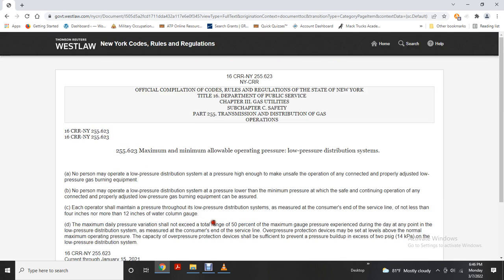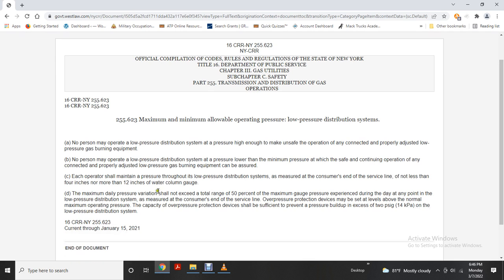Minimum and maximum allowable operating pressure, low pressure distribution. No person may operate a low pressure distribution system at a pressure high enough to make unsafe the operation of any connected and properly adjusted low pressure gas burner equipment. No person may operate a low pressure distribution system at a pressure so low that the minimum pressure needed for safe continuing operation of any connected and properly adjusted low pressure gas burner equipment cannot be assured. Each operator must maintain pressure throughout the low pressure distribution system, measured at the consumer end of the service line, of not less than 4 inches and not more than 12 inches of water gauge.